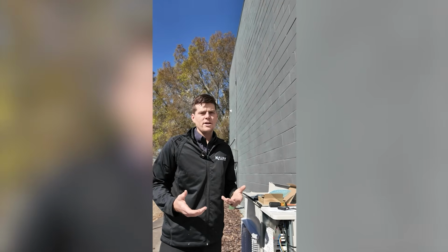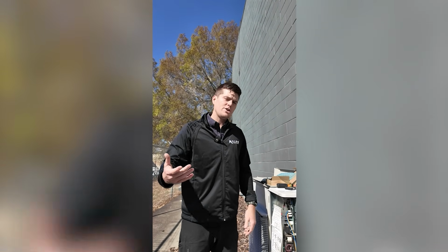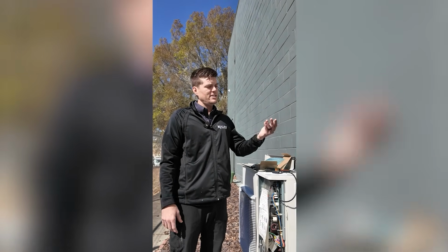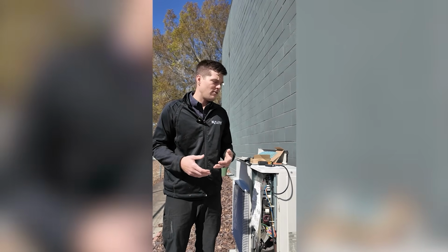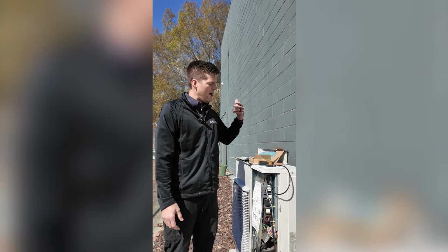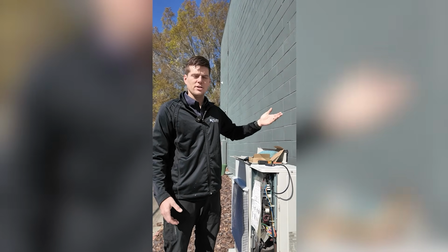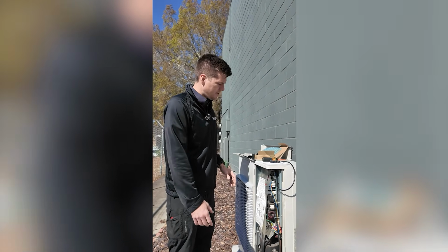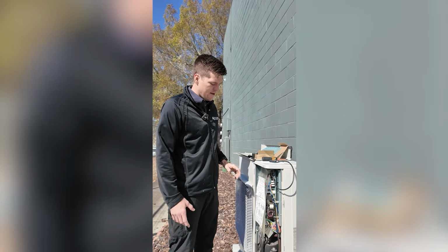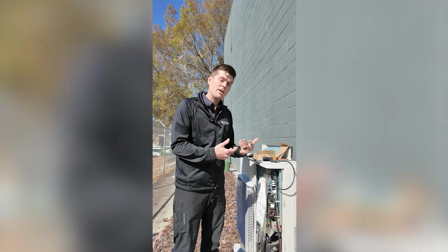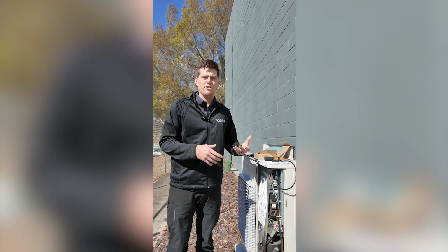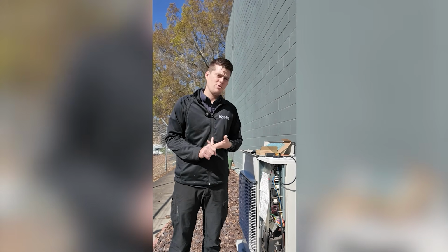Remember, the longer the recording can be on a system like this, the more information we have to troubleshoot. Is it consistently defrosting? How long is the defrost cycle? What is the indoor unit doing? Why are certain protection controls being enabled at certain times of the day? All of those things are recordable from something like this on a system like this. Now I can come here if there is an error code and I can troubleshoot that error code. Maybe it's a bad fan motor, maybe it's an inverter board error code.